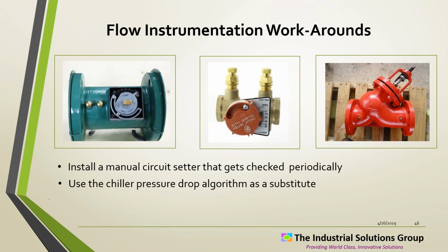Another way, some of our equipment like chillers are really good for this. They'll look at the pressure drop. They have some internal pressures, and they back calculate flows based on their pressures. So I'm not an advocate of putting in extra instrumentation. If we can be creative and make use of packaged equipment and its data, then by all means we should be doing that.